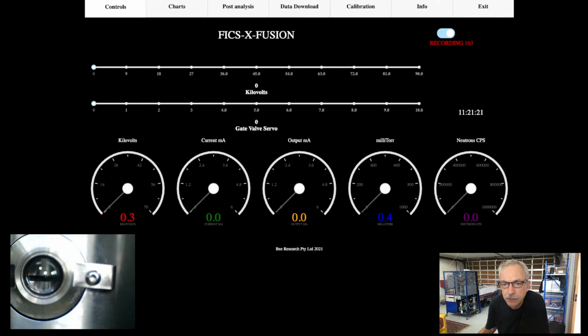So the first thing I'm going to do here is slowly bring the voltage up. As you can see, this is the input voltage in kilovolts, and I'm going to bring that up very, very slowly. So we're now at 18,000 volts, and with the turbo pump going and the valve fully open, the vacuum pressure is very low, and we're not seeing any breakdown. We're not seeing any Paschen breakdown in the plasma at all. So we will continue to increase this very slowly, and with a bit of luck, no arcs.